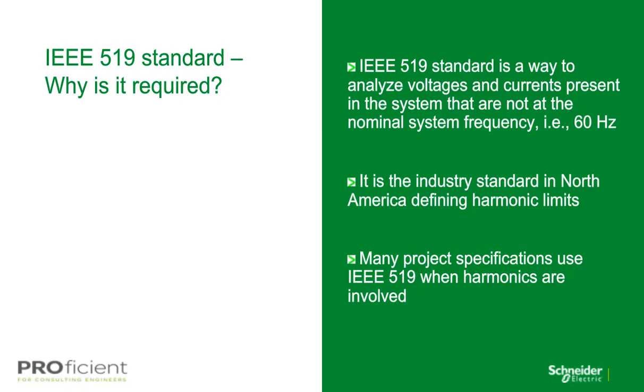So the IEEE 519 standard. First question: why is it required? The method for handling harmonic specifications to date has really been somewhat subjective. And per IEEE, their definition is that it sets parameters for the design of electrical systems that include both linear and nonlinear loads. The voltage and current waveforms that may exist throughout the system are described, and the waveform distortion goals for the system designers are established. The interface between sources and loads is described as the point of common coupling, also known as PCC. And observance of the design goals will reduce interference between the electrical equipment.